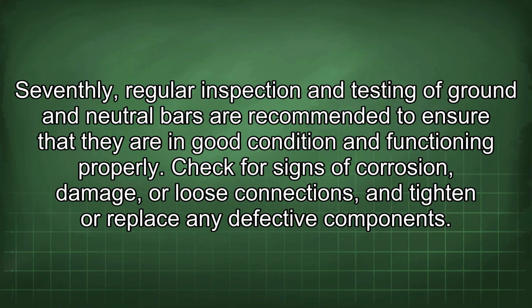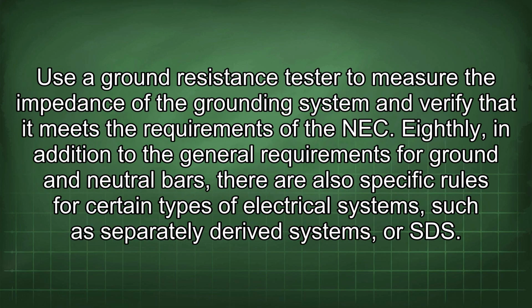Seventhly, regular inspection and testing of ground and neutral bars are recommended to ensure that they are in good condition and functioning properly. Check for signs of corrosion, damage, or loose connections, and tighten or replace any defective components. Use a ground resistance tester to measure the impedance of the grounding system and verify that it meets the requirements of the NEC.